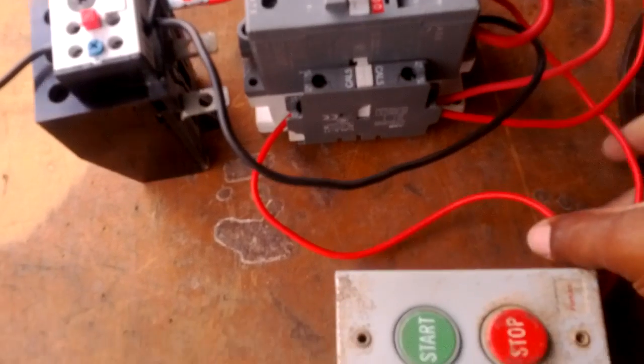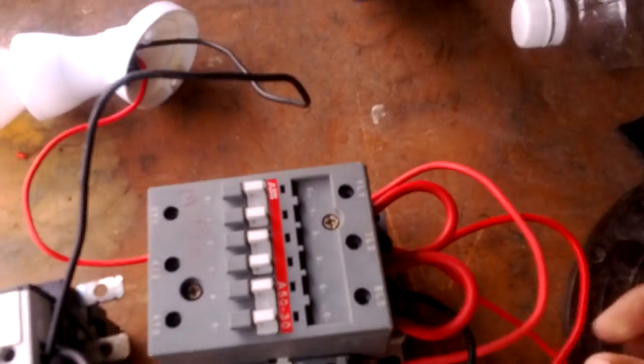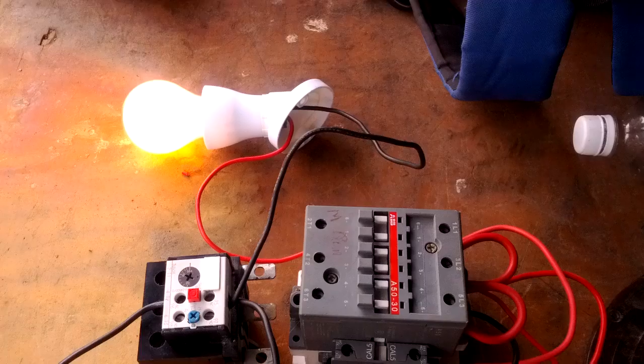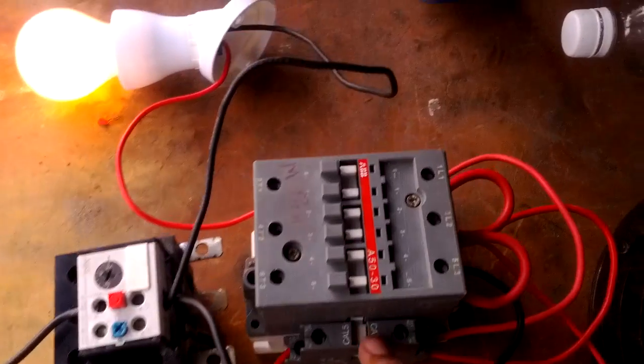So keep in mind, two wires from the normally closed part of your stop button. One wire is for the holding circuit, and this wire is for my coil itself. So when my coil slams in, it stays in. This is my holding circuit.